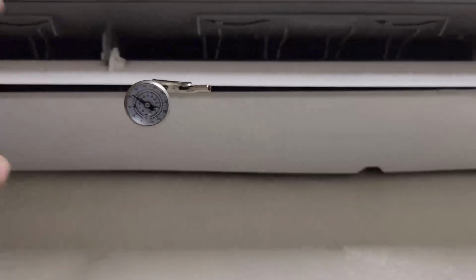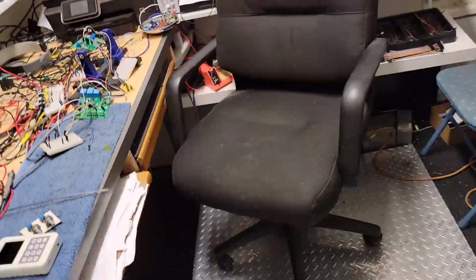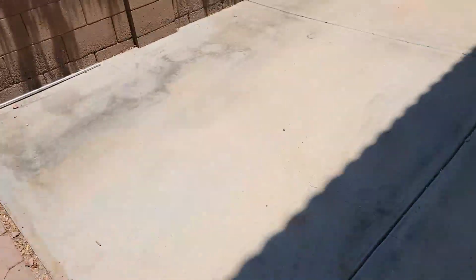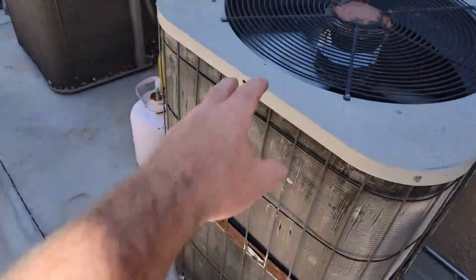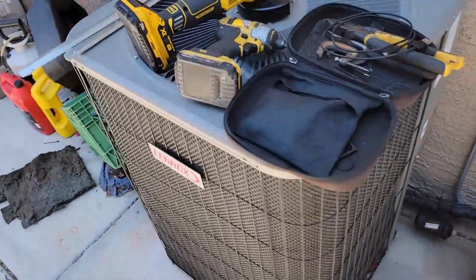So now that we know the tank is at 132, the room's at 81, I got like 63 or something. Kind of crappy. Got like 18 degrees split right now. Let's go. I'm going to add a couple shots of refrigerant and go see what it does. Got the old Goodman running. Got the Lennox running.